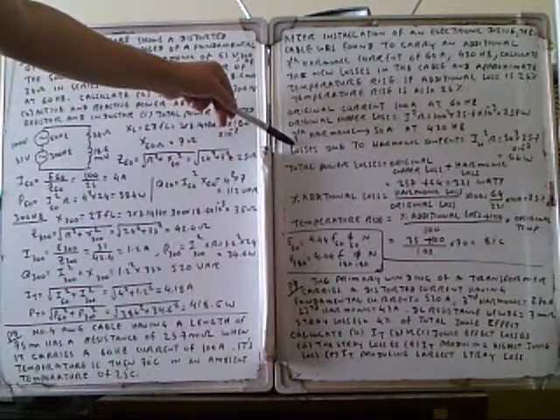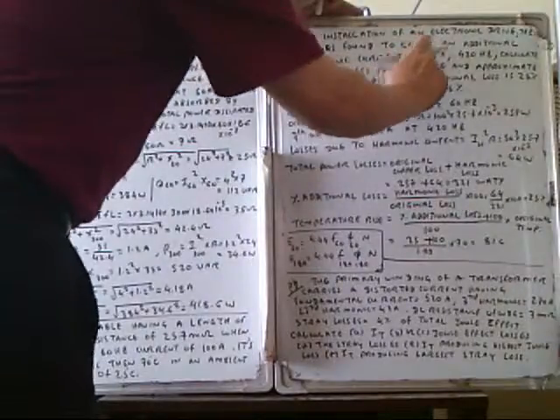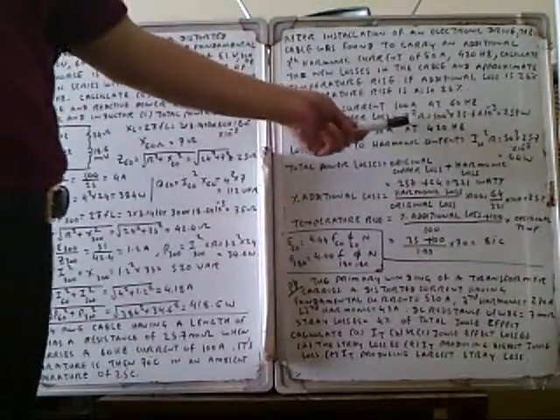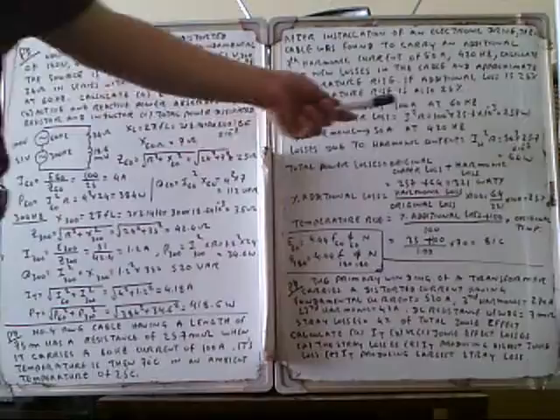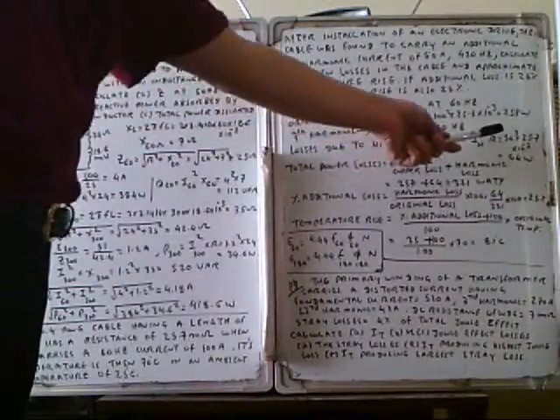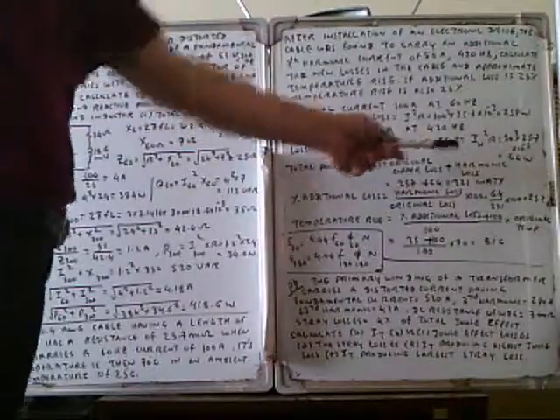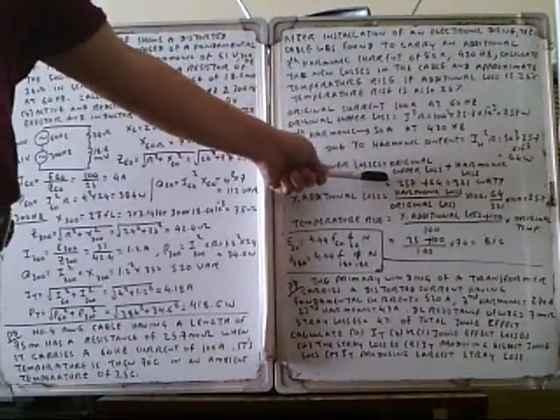The 7th harmonic is carrying 50 amps additional current. 50 amps at 420 Hz. We calculate the additional loss of I squared times R. 50 squared times 25.7 times 10^-3 equals 64 watts. The total power loss is the original copper loss plus harmonic loss. Original is 257, harmonic is 64, you get 321 watts.